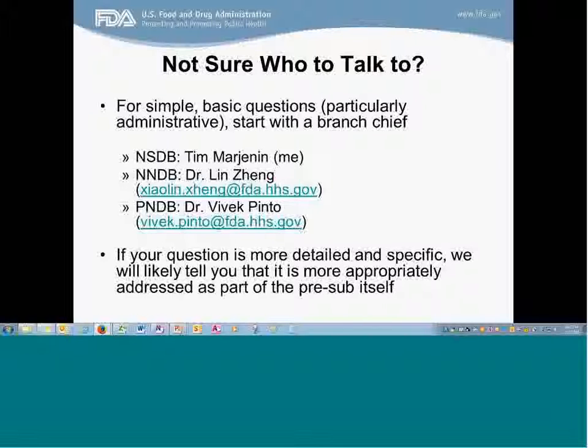Question. For FDA ODE IDE application reviewers, are there generally expected best practices for particular situations? For example, for a novel device, the selection of animal models, such as large animals versus small animals. I think that's a perfect reason to come in with a pre-submission to discuss it. It's really a matter of what you think is the best approach that fits your particular needs. If there's no guidance document or standard, if there's nothing out there in regulatory communication that says what we expect, then it's really up to you to say, here's what we propose to do, here's why we think it's the best approach. It's better to do that as a pre-submission than as part of an IDE, because we can be more interactive, have a meeting about it, and discuss our concerns and feedback with you.